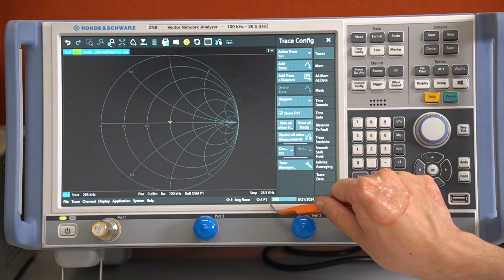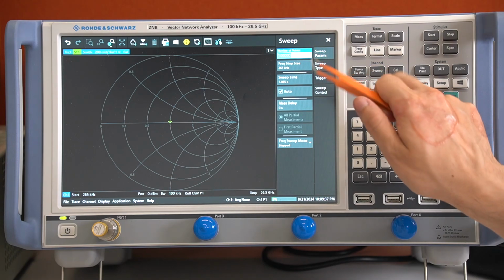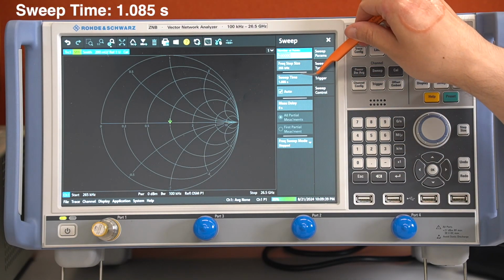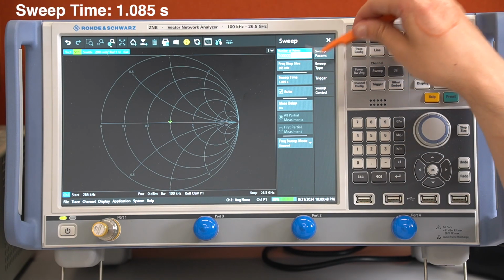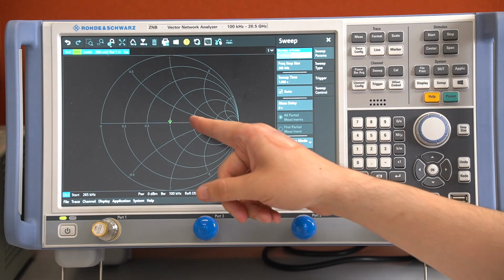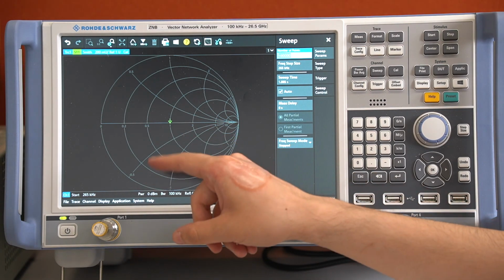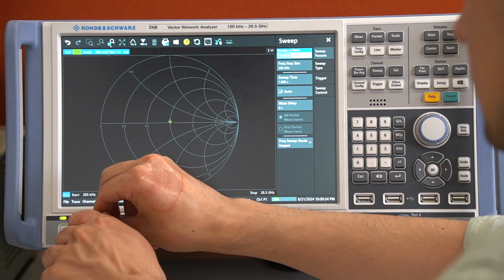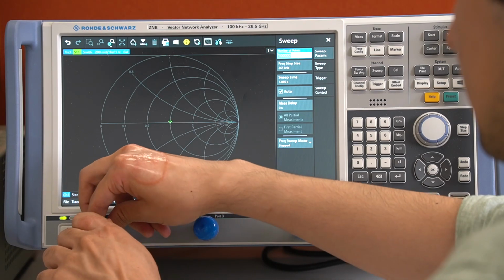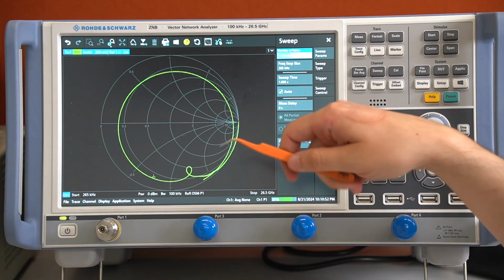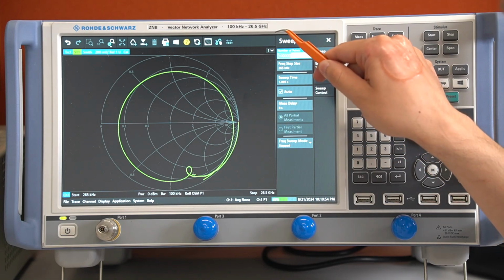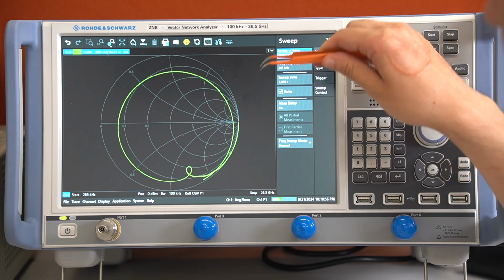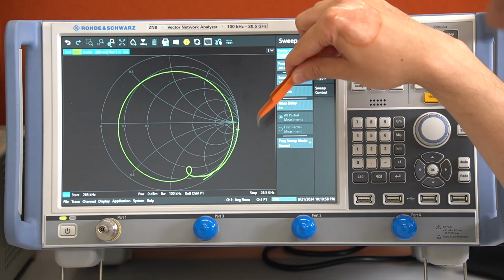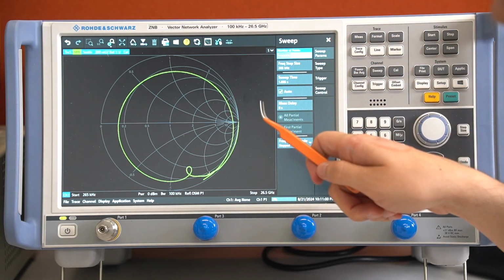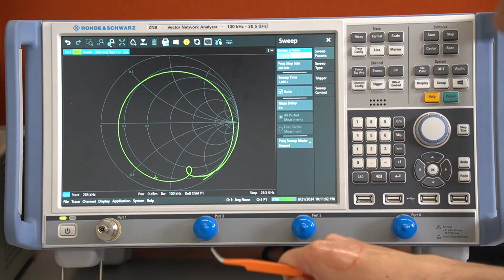So we get rid of port 2, which means that our sweep time is now reduced to the half, to approximately 1 second. And we can now see here, this is our match. It's a really good broadband match. And if we plug it off, this is now S11 up to 26.5 GHz. And as you can see here, this Smith chart looks way better than with the self-made calibration kit.